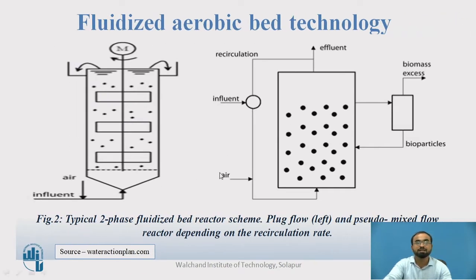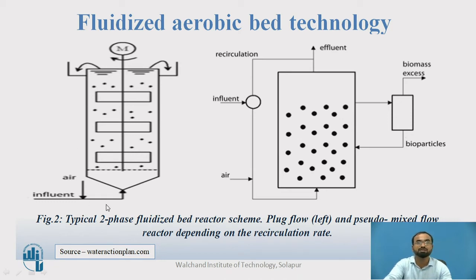This is the typical two-phase fluidized bed reactor in which solids and liquid — that is wastewater — are present in the bioreactor. If you see the left part of the diagram, you will understand that no air is provided inside the bioreactor; only two phases, solid and liquid, are put inside. Air is then made to push inside such a reactor with the influent. As we need to provide a large velocity of upflow wastewater, some part of the effluent again has to be recycled; otherwise, no biofilm MLSS will be maintained inside the reactor.